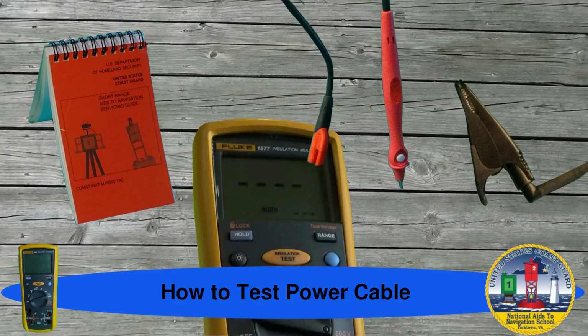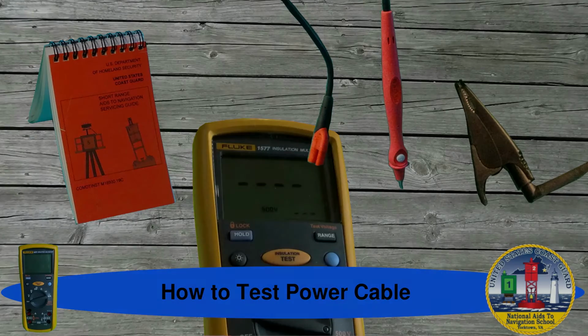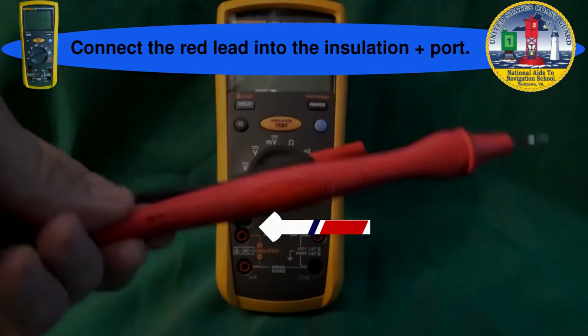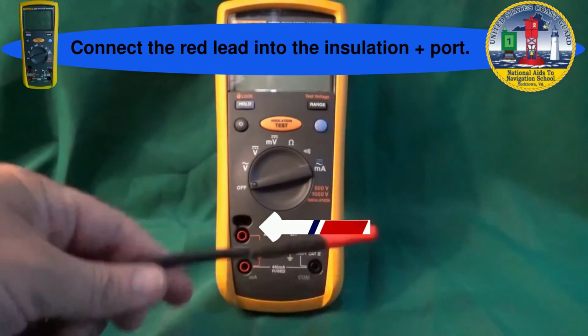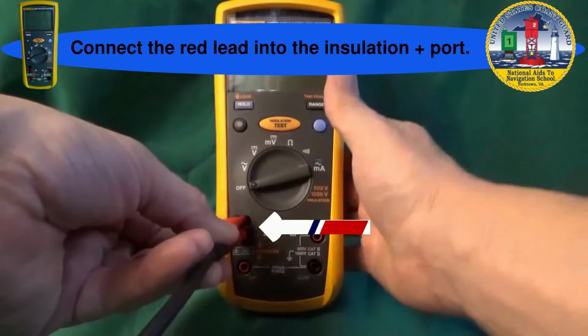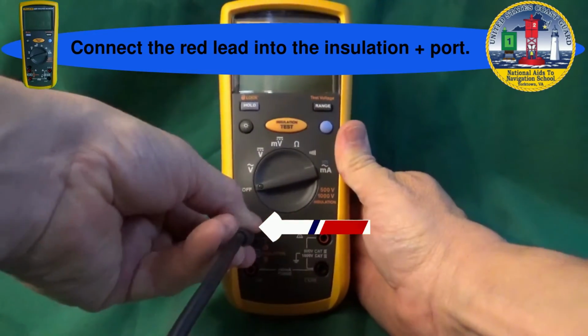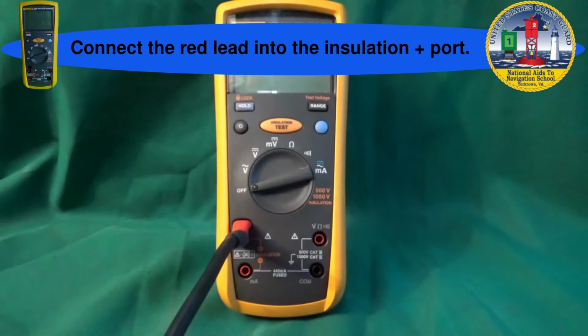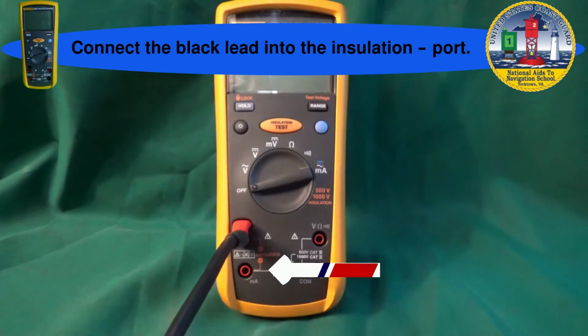Testing servicing cable will help catch discrepancies before they occur. First, set up your meter to test insulation. On this Fluke 1577, the insulation test leads are plugged in on the bottom left of the meter. Plug the red lead in the insulation plus port, and the black lead in the insulation negative.